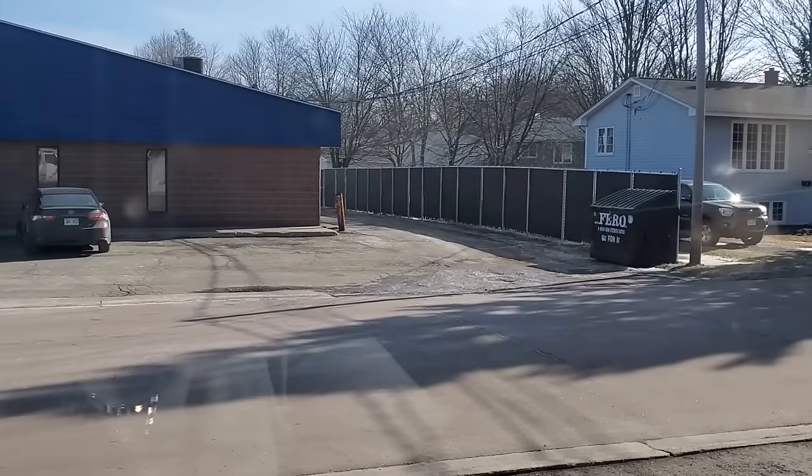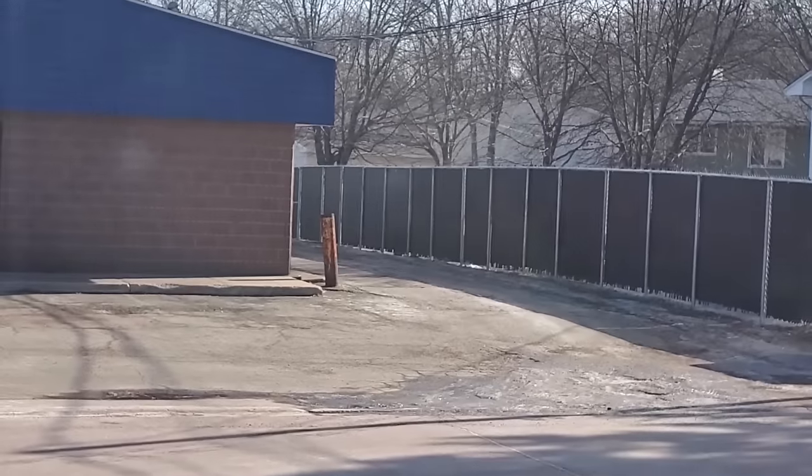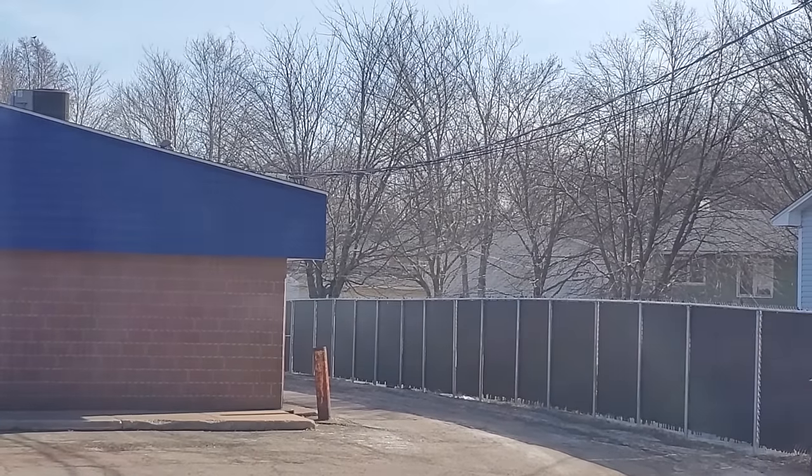Where this is underground, first thing we're gonna do is open those pad mounts. Honestly, I'm hoping I find something. Hopefully I find a termination that's all blown to pieces with enough slack that we can splice on a new one. If there's not, we could be in a huge mess here. This is all direct buried 7200 volt lines going through right where that fence is into that neighborhood. Yeah, it's not good at all.